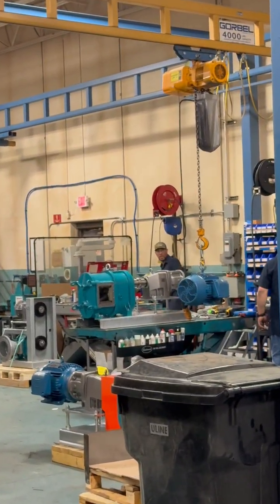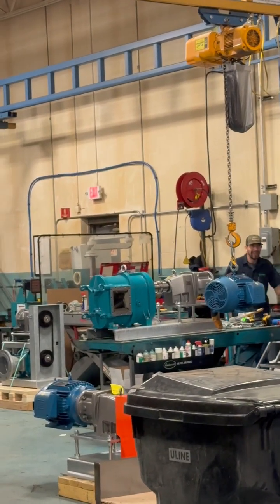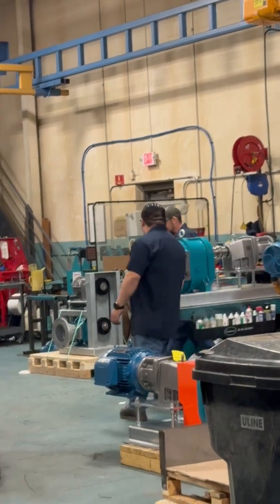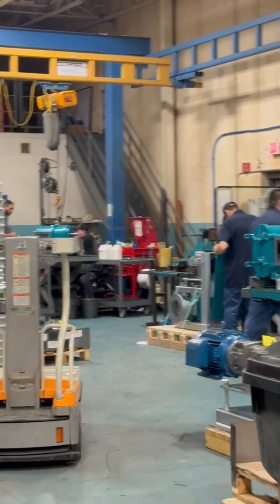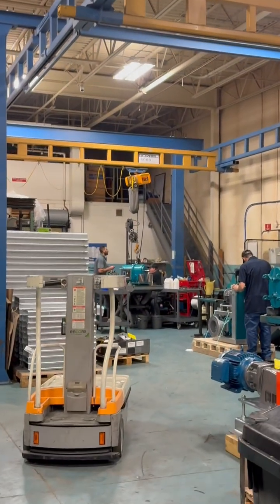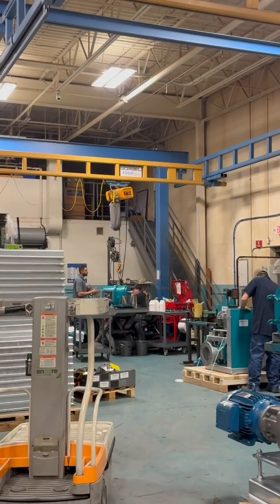And then at the other end of the shop here, we have an FAT machine, so we can actually do a factory acceptance test that'll test the pump head. If we have to change mechanical seals or anything of the sort, we can check the integrity of the seals as well as the torque requirements of the particular pump to turn over.